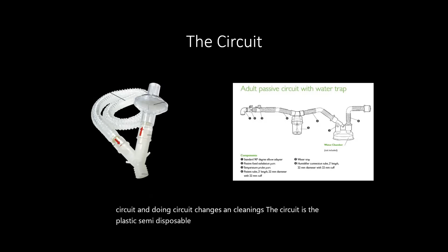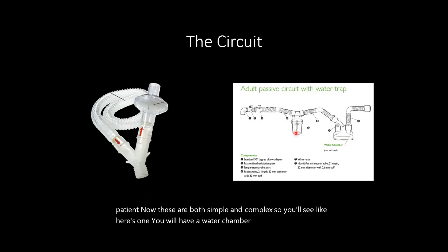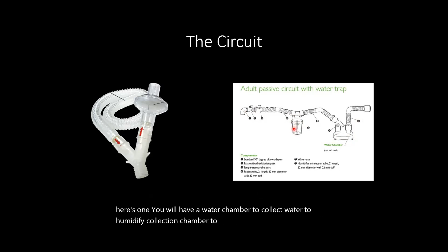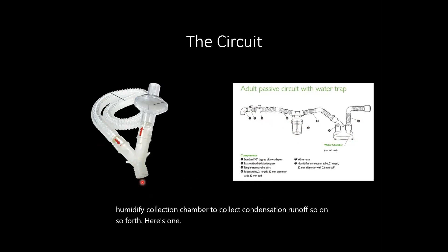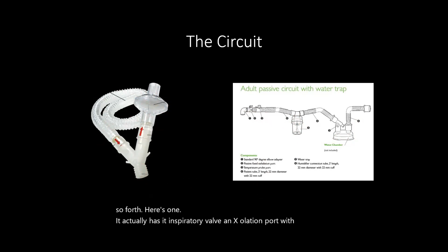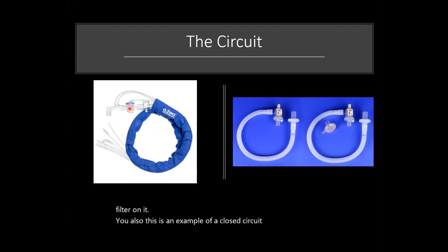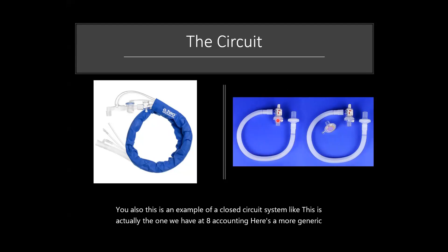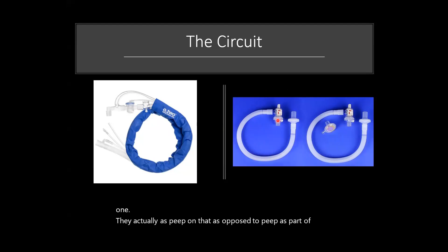The circuit is the plastic semi-disposable tubing that runs from the ventilator to the patient. Now, these are both simple and complex. So you'll see, like, here's one. You will have a water chamber to collect water to humidify, a collection chamber to collect condensation and runoff, and so on and so forth. Here's one that actually has an inspiratory valve and an exhalation port with a HEPA filter on it. This is an example of a closed circuit system. Like this is actually the one we have at Ada County. Here's a more generic one that actually has PEEP on that, as opposed to PEEP as part of the ventilator itself.